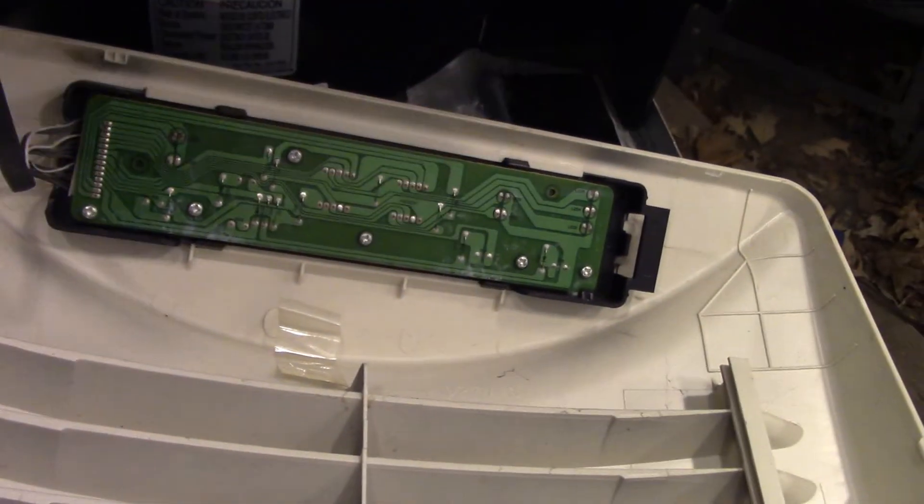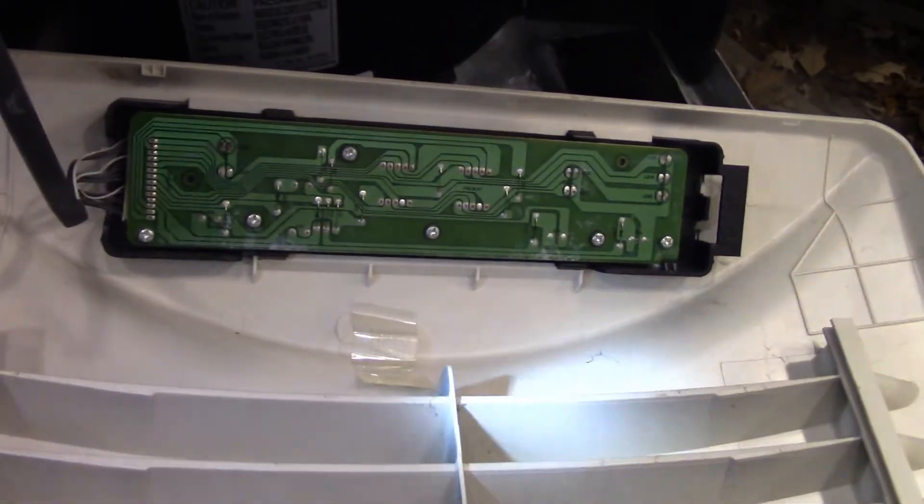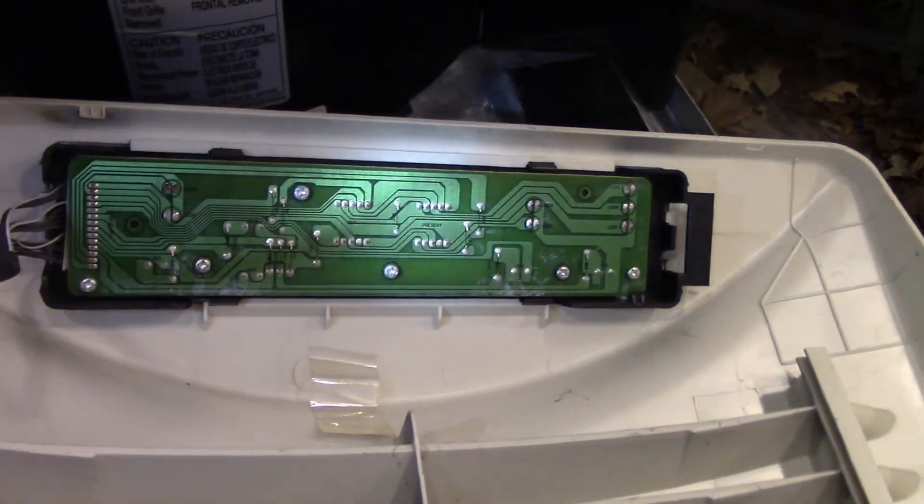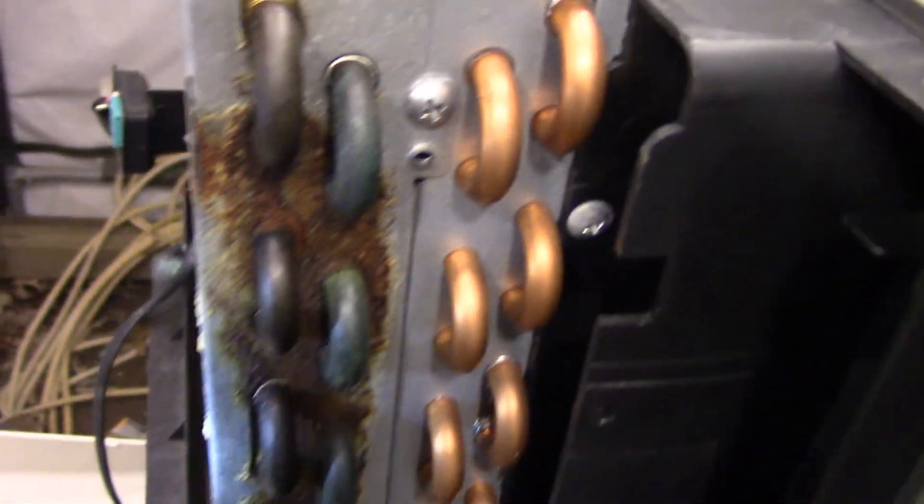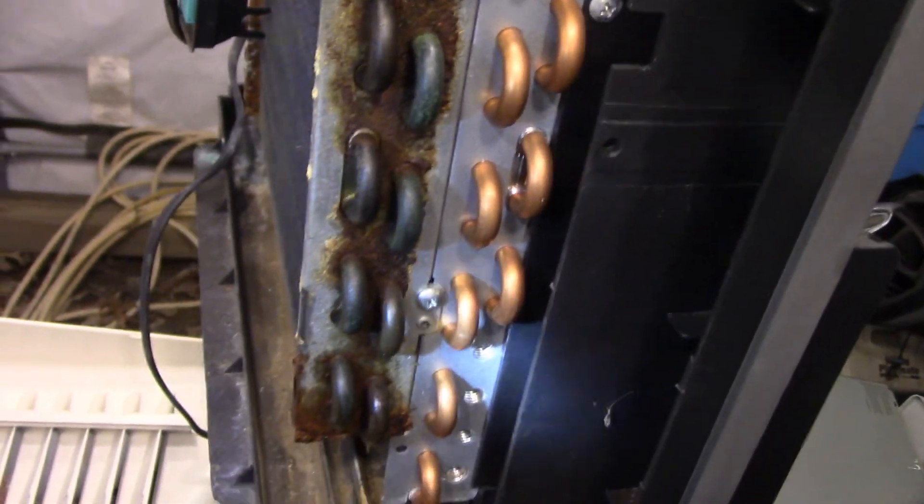That is the capacitor and where all the controls are that runs down to this control board here. It does not look to be too bad. It does not look like it has had any water damage or anything to it. There is some surface rust on that unit, but nothing that is really damaging that I can see.